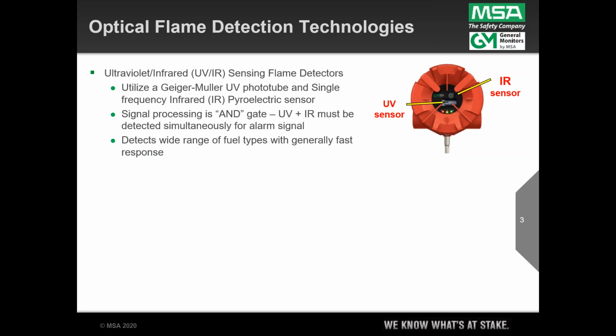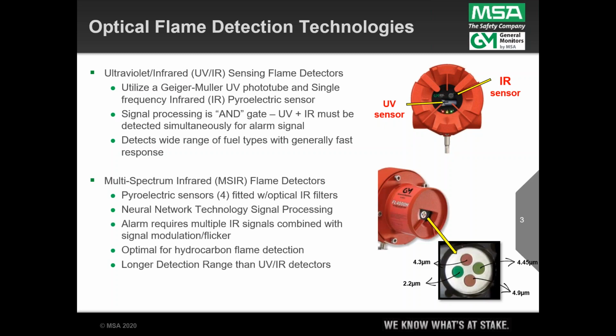But then in the early 2000s, with the availability of 32-bit microprocessors, it was possible to measure four different wavelengths of infrared in the same instrument. By using a more sophisticated algorithm, and ours is called NNT, or neural network technology, the bottom line is that this 4IR detector doubled the detection range, and still does, of the UVIR detector to the same size fire. It is a hydrocarbon specific technology, meaning you can't use this for a hydrogen fire or a sulfur fire or a magnesium fire. But on hydrocarbon fires, either liquid or gaseous, it basically doubles the range as compared to UVIR detectors.